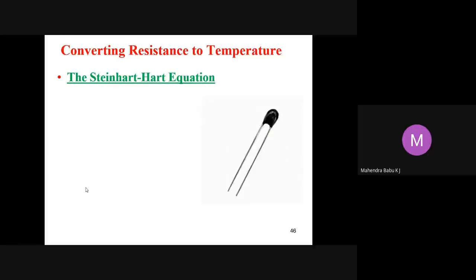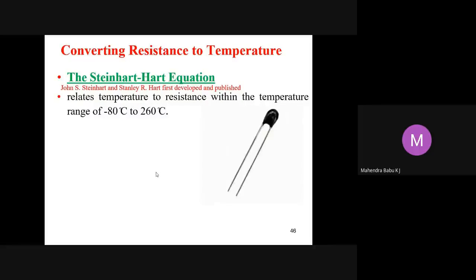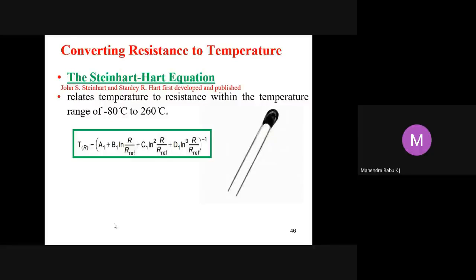There are many methods to convert resistance measured using RTDs or a thermistor to a temperature. One of the commonly used methods is the Steinhart-Hart equation, named after John S. Steinhart and Stanley R. Hart, who first developed and published the equation. The equation relates the temperature to a resistance within the temperature range of minus 80 degrees Celsius to 260 degrees Celsius. According to the Steinhart-Hart equation, the relation between temperature and the resistance is given by this.